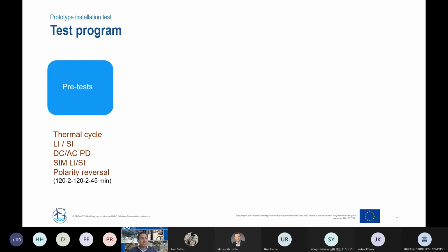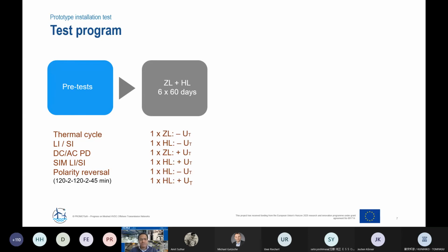Also superimposed impulse application, both lightning and switching impulse, have been applied on top of DC, and also application of a DC voltage for each polarity: 2 hours positive polarity, and after 2 minutes we change polarity again, and for negative polarity another 2 hours, and reverse back to positive for 45 minutes. Once we make sure everything is okay, then the long term test itself starts.